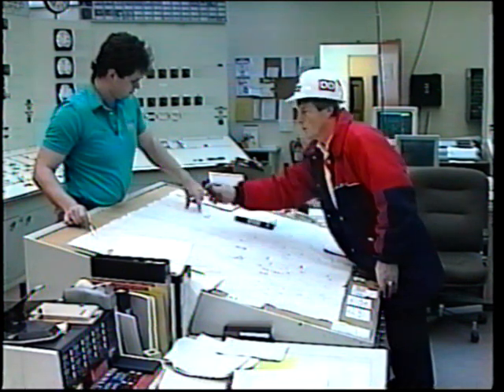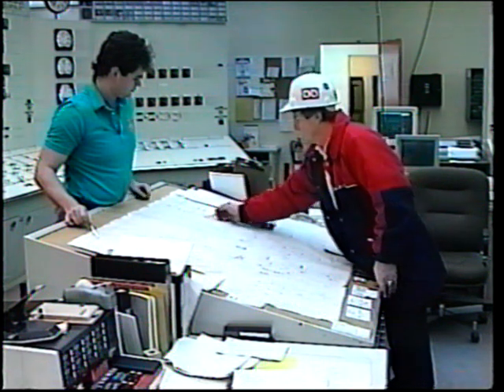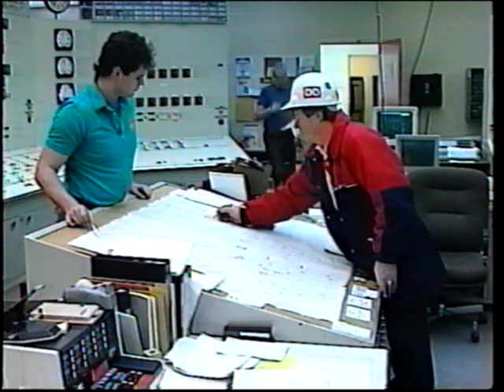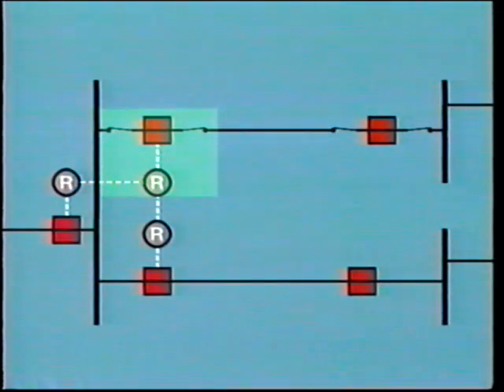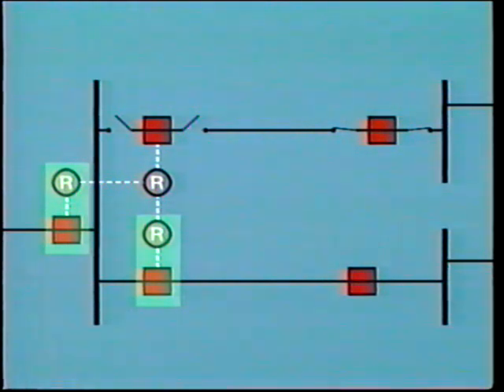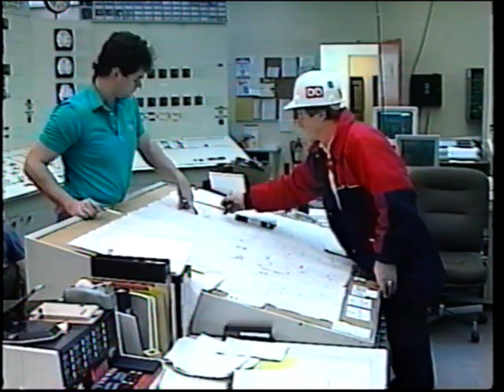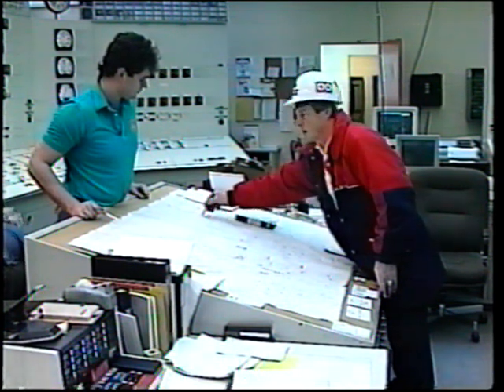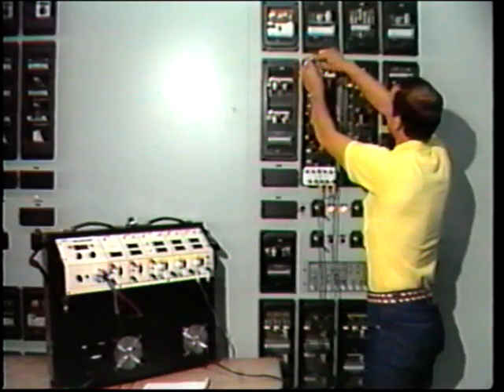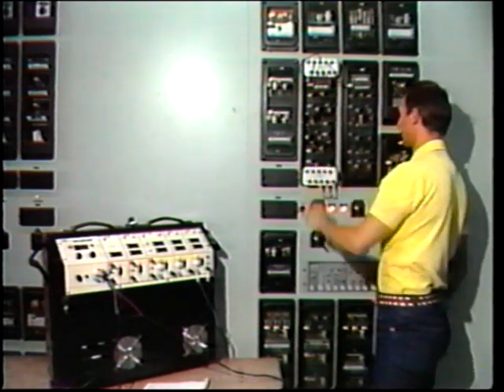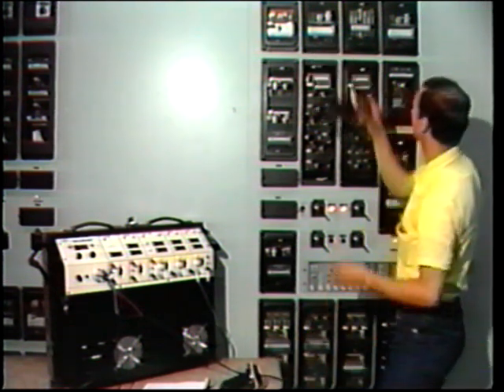Good cooperation between the operator and relay technician is vital, especially during the preparation stage for testing. Be sure to let the operator know the extent of your tests and the time period. It is to be hoped that the equipment under test can be taken out of service and isolated so that the tester's activities will not impact system operation. However, this may not be so easy, because in many schemes, protection on the isolated circuit may have some interconnection with a protection scheme on a neighboring live circuit. In this situation, special precautions must be taken by the relay technician to prevent interference with the live circuit. He must also alert the operator to any possible problem conditions that could arise, even remotely, so that the operator can prepare some contingency plan. The operator should also be informed of the time which will be required for the tester to abandon the tests, disconnect his test equipment, and make the line available in case of emergency.